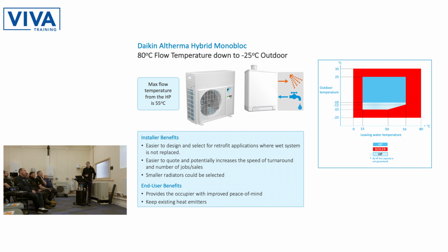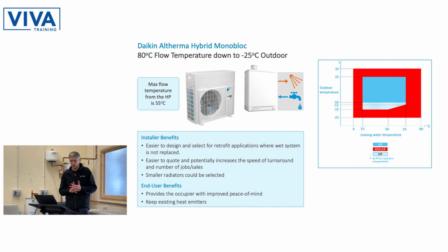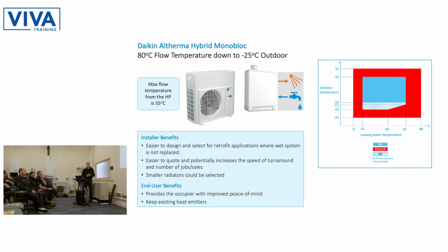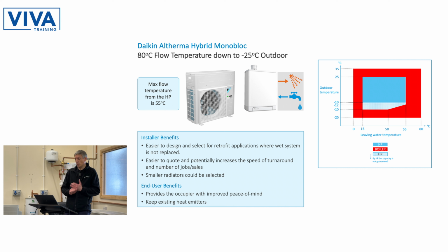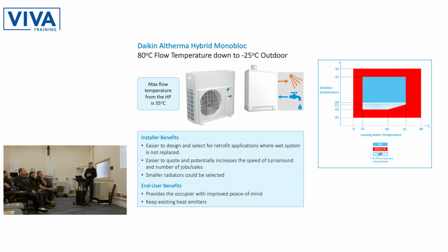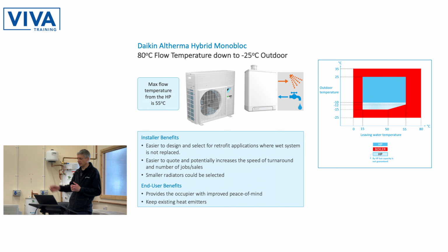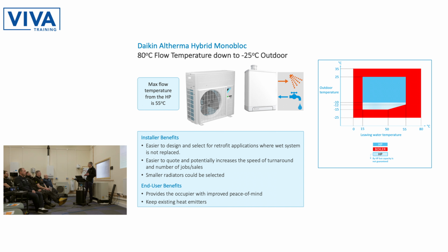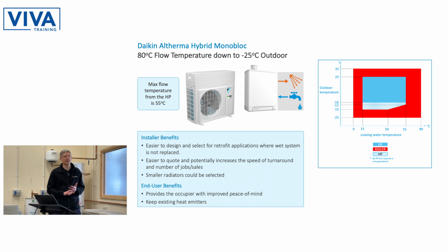So yeah, I've said it before, keep the existing radiators. We are actually looking at the moment at the possibility of just being able to fit the boiler first. So one of our targets with this is the distressed purchase, as we call it, where the existing heating system, the boiler's broken down. You want to get that back up and running as quickly as possible. So we're looking at the moment at just the possibility of installing the boiler first and then fitting the heat pump to it later. Now that boiler is customised for us specifically. It expects to talk to the heat pump. So if you just put that in by itself as it stands and the heat pump isn't there, no, I don't want to do that because I haven't got the heat pump to talk to. Don't know what I'm doing.